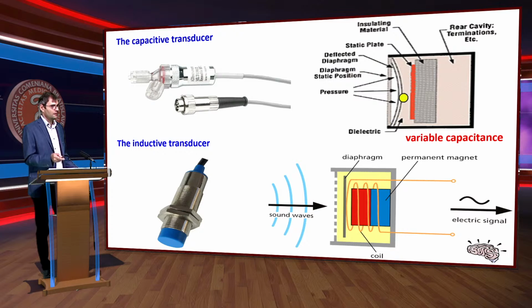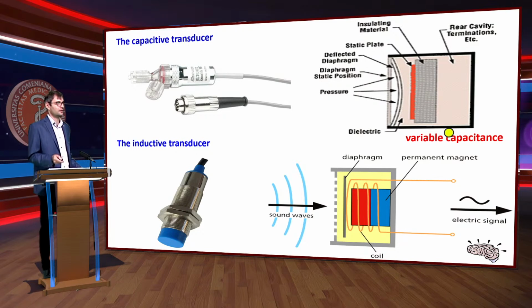This capacitor works on the principle that you have a membrane, and when pressure is applied, the distance between the membrane and the static plate changes. This changing distance creates a variable capacitance, which is converted into a different voltage, and the signal is created.